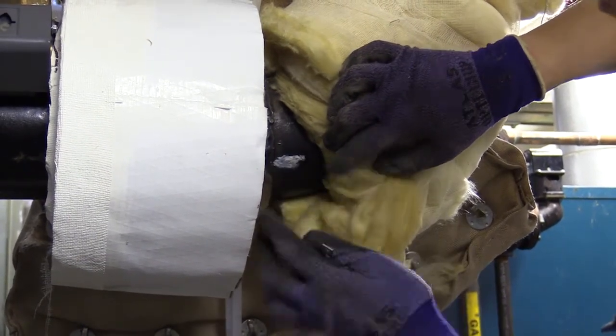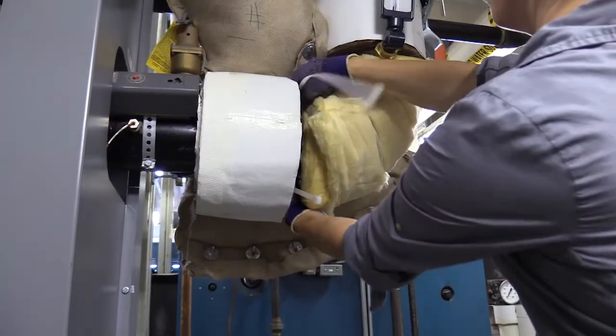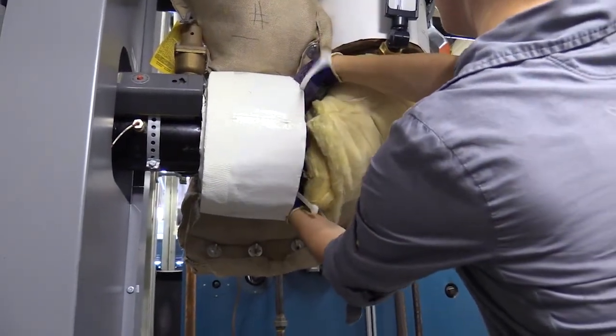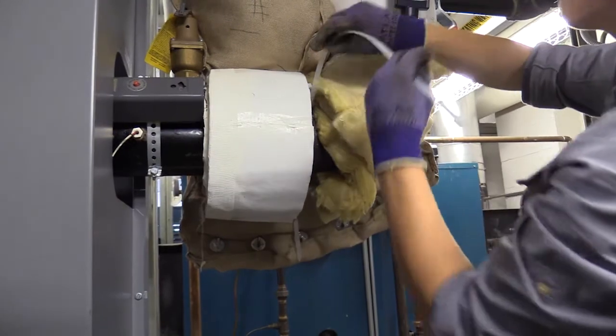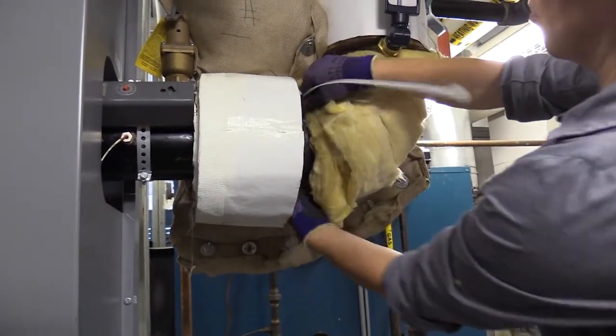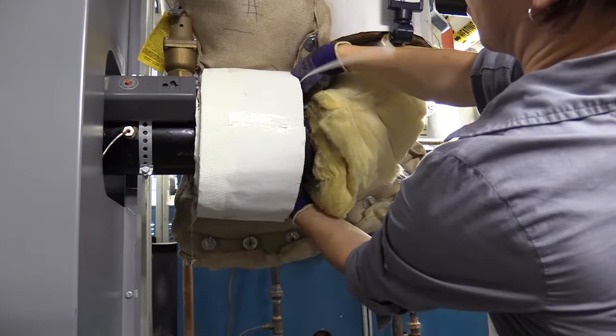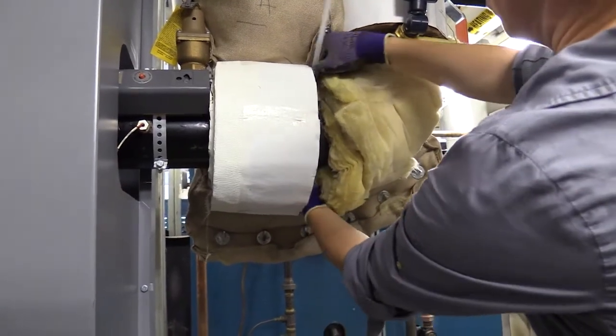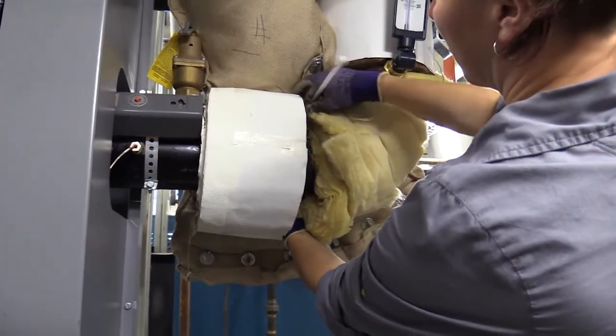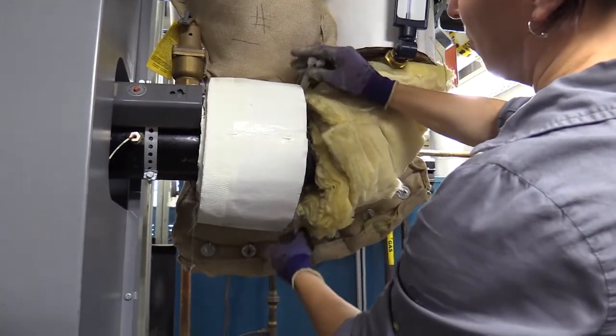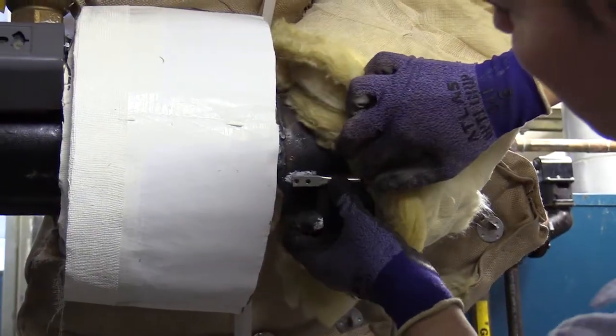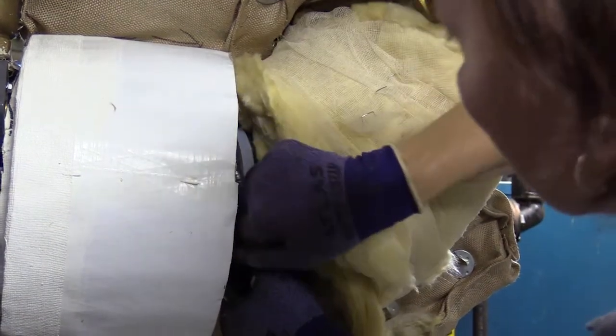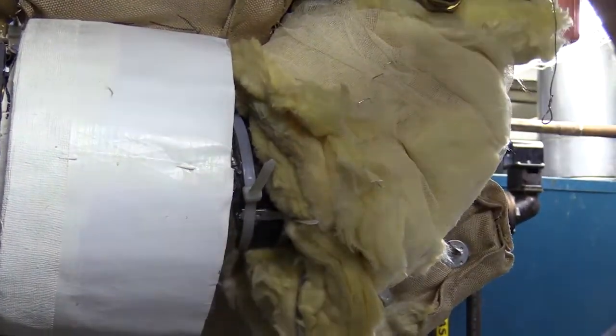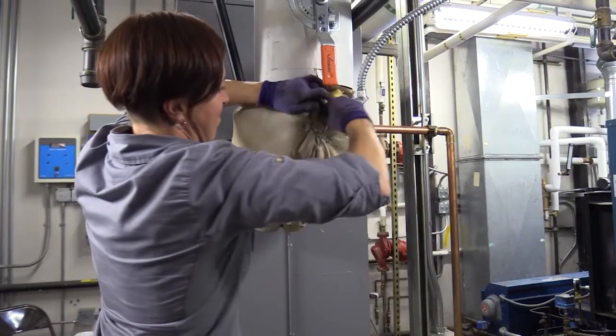And before placing the sensor, you want to prepare a way to secure it to the pipe, ideally with a hose clamp. In this case, I used a long zip tie. This is a condensing low temperature boiler, but a zip tie wouldn't necessarily be appropriate in higher temperature applications or for longer term. So really a hose clamp is ideal. So you place the sensor so that the cable runs in line with the pipe, secure it, and then replace the insulation.